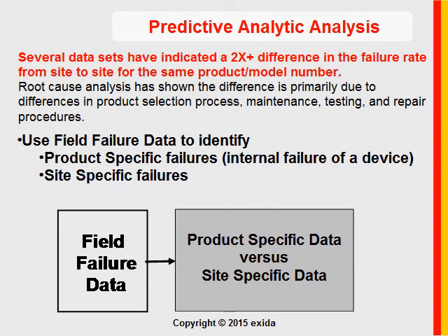If you collect data, you will be able to identify and sort the difference between product-specific failures and site-specific failures. What I'm saying is, if you have a good data collection process that has been validated and reasonable, and yet you still find a failure rate that's higher than it should be, you have a problem that you can fix. And we've found many examples like this. And when those people identify those problems, they reduce the failure rates of their equipment.